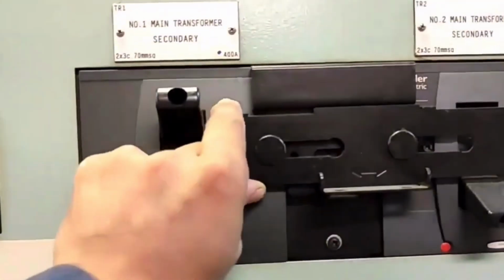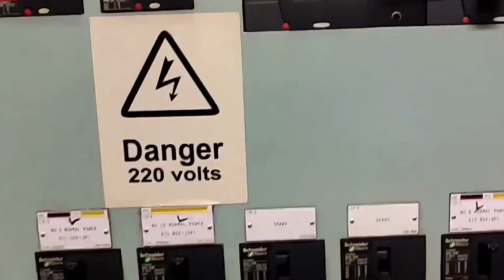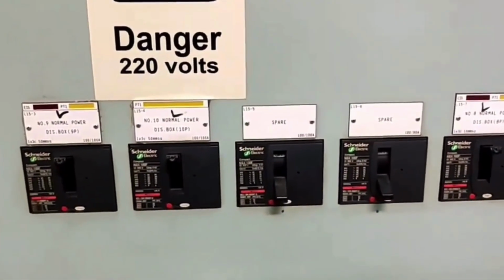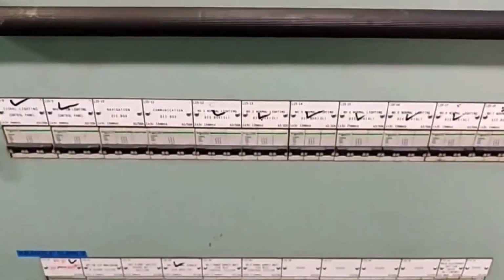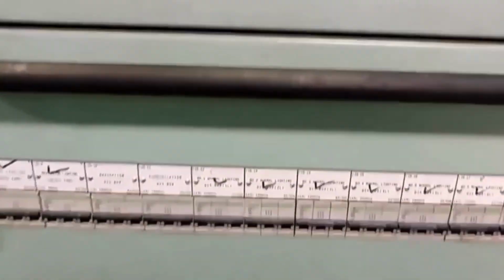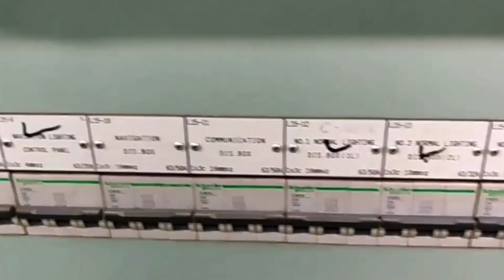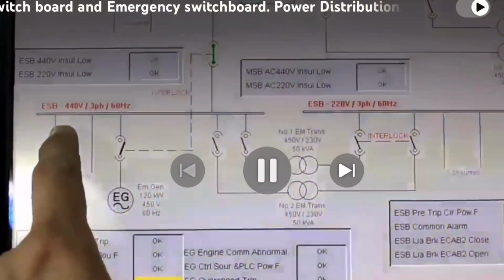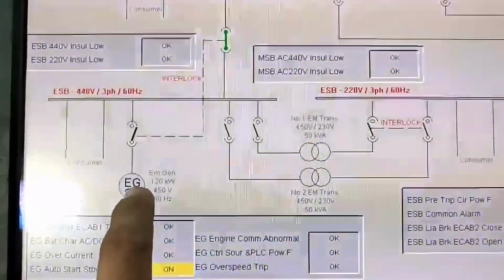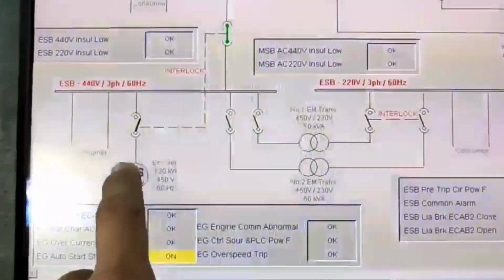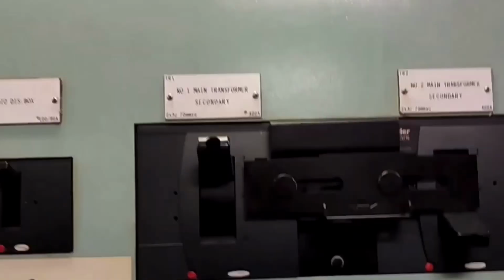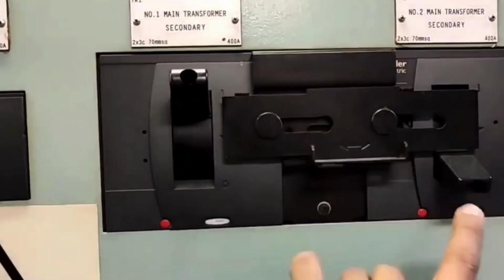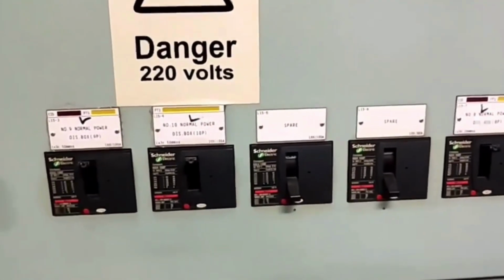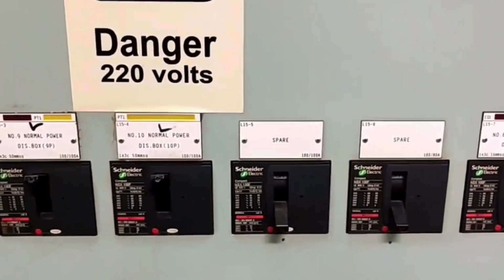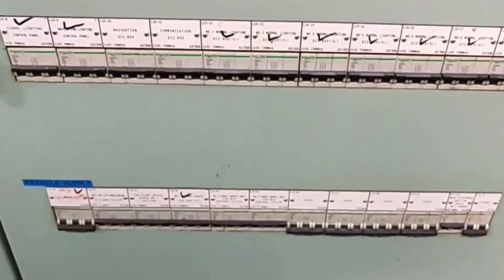Now we move to the main switchboard 230 section, where safety and interlocking systems play a critical role in reliable power distribution. This section is designed to ensure that no unsafe switching operation can occur during live conditions. Mechanical and electrical interlocks work together to prevent accidental breaker closure or isolation errors. Before any operation, proper sequence checks and protection relays must be verified. During factory trials and onboard vessel installation, insulation resistance, continuity, and functional interlock tests are carried out to ensure full compliance. This guarantees safe operation, system stability, and protection of both equipment and personnel.